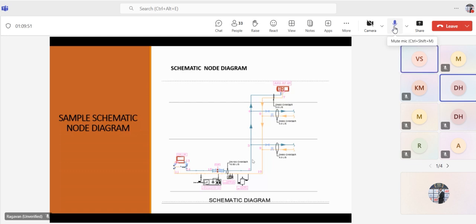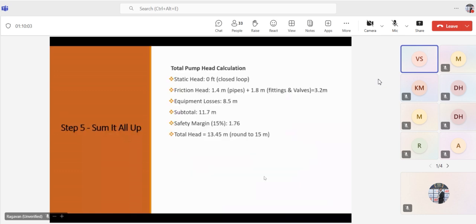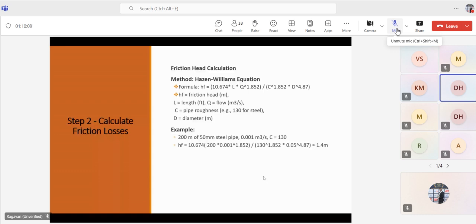Yeah, this is what I said. That one is the Hazen-Williams equation. In this equation, you have to put this value. For example, you have the fittings. I'm asking what should be the Q value to calculate the friction. The Q value is the flow rate, right? If the flow rate varies from one point to another point, between the points you have the flow rate. For example, if the flow rate is 10 liters per second at point 1, how do you define the flow rate at point 3? This is what I said.